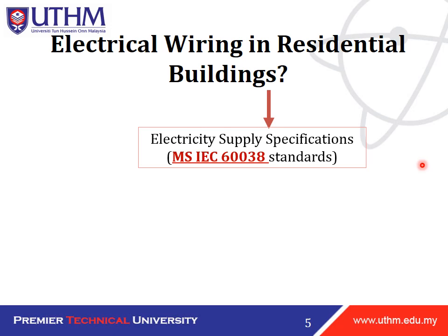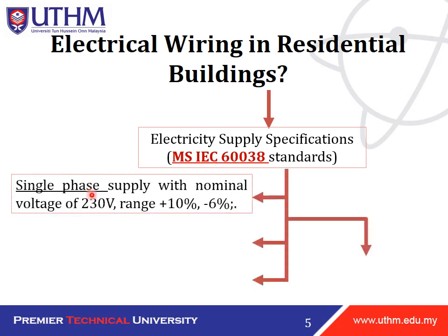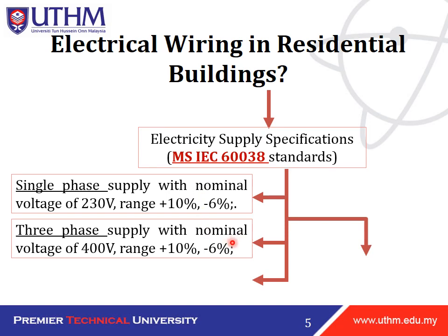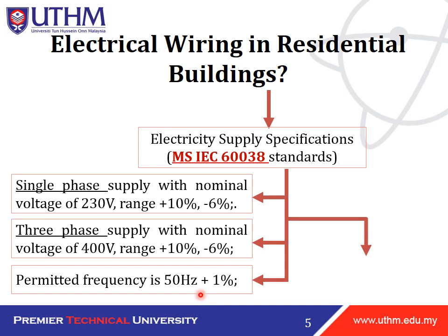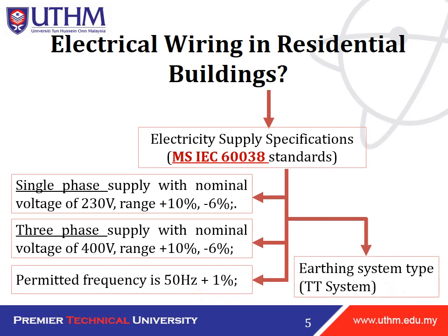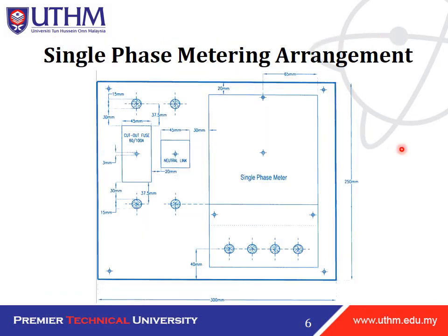Electrical wiring in residential buildings follows the electricity supply specification MS IEC 60038 standard. In this standard, we have a single phase supply with nominal voltage of 230 with range plus 10% and minus 6%, and also three phase supplies with nominal voltage of 400 with range plus 10% and minus 6%, and then the permitted frequency is 50 Hz plus 1%, and also the earthing system type, which is TT system.